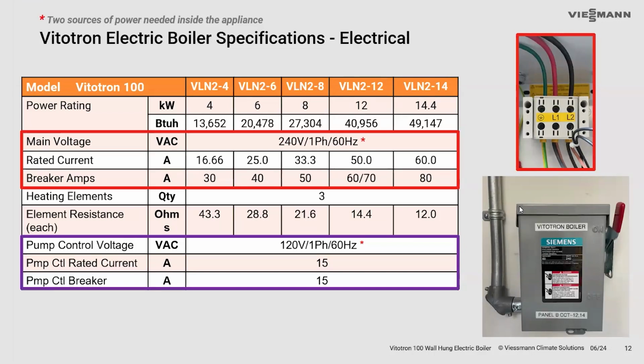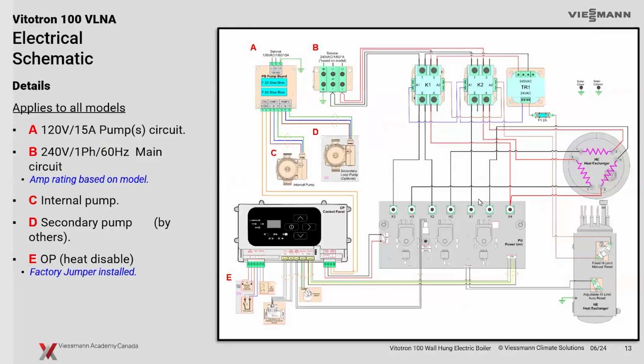So the 240 volt is for powering the elements to heat the boiler. You also need a separate 120 volt entrance to come into that for the pump outputs that are available on the boiler itself. So just wanted to review that, two separate powers. This is what it would look like essentially as a quick review here. A is your incoming power 120 volt that would come in to terminate on the top here, and that's going to operate your pumps. So we'll have a look at that in a little bit, how that all looks in a bit more detail. But just to show you separately here that there does require two power sources.